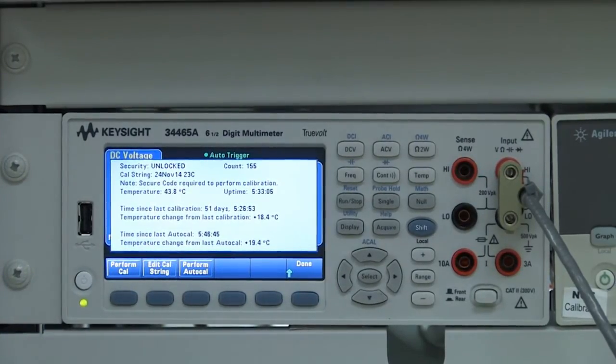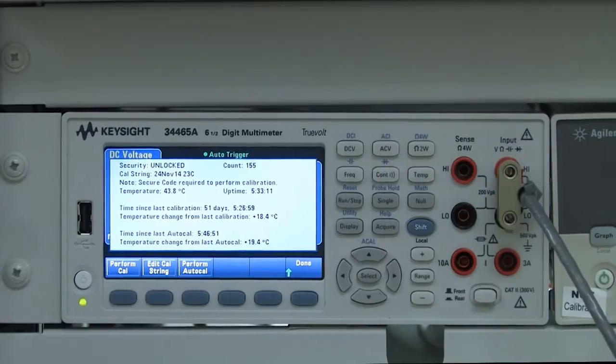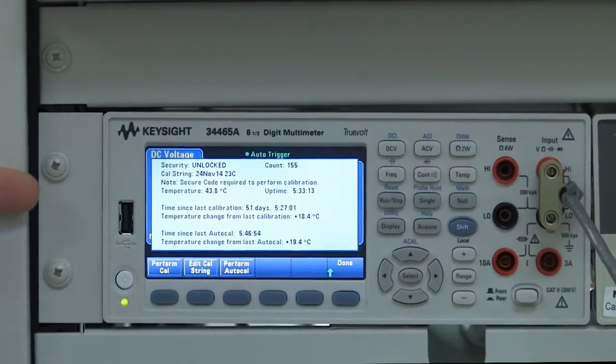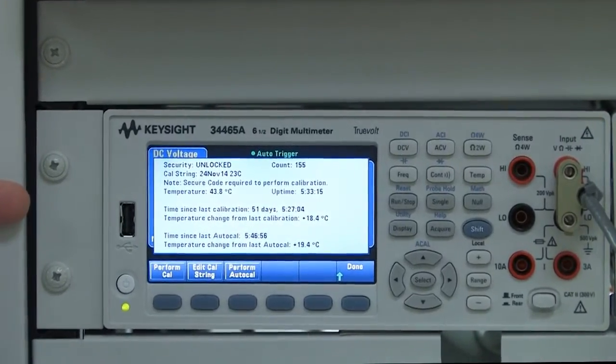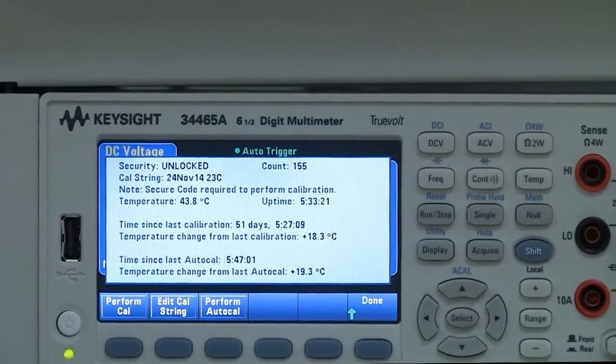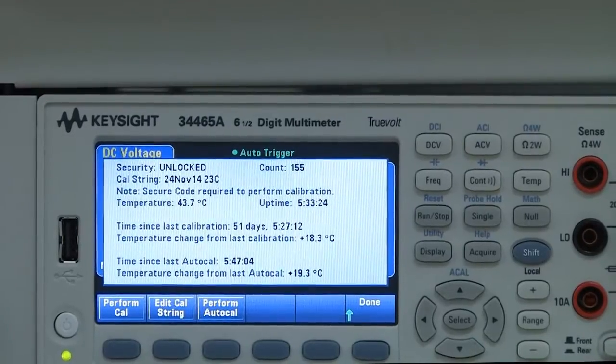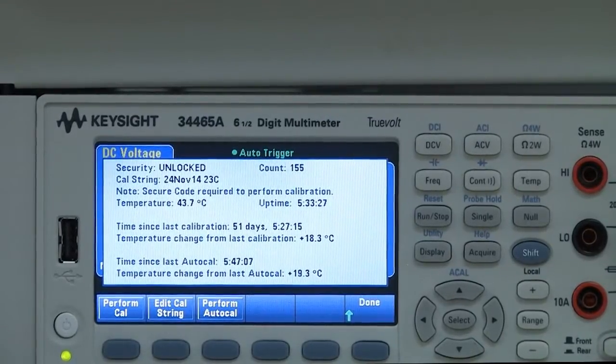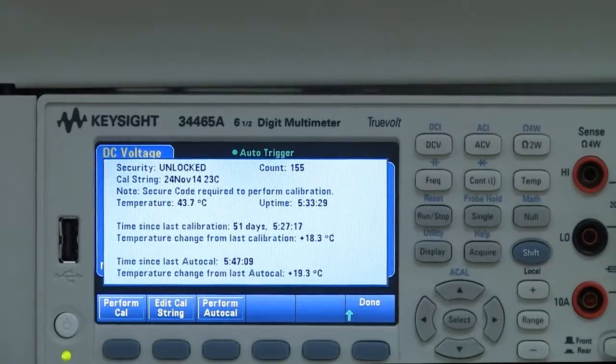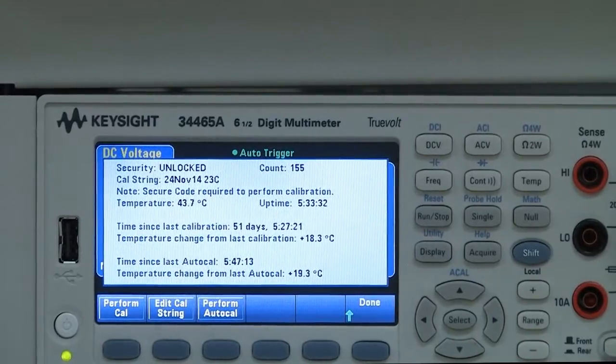Using this method brings up a calibration window which is very useful. The calibration window includes information such as the current internal temperature of the instrument, the up time or the time the instrument has been continually powered on, the time since the last full calibration, the difference in temperature since the last full calibration, the time since the last auto cal, and the temperature since the last auto cal. For our application, we have seen the temperature increase by 19.3 degrees.